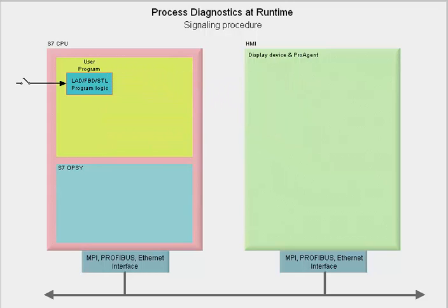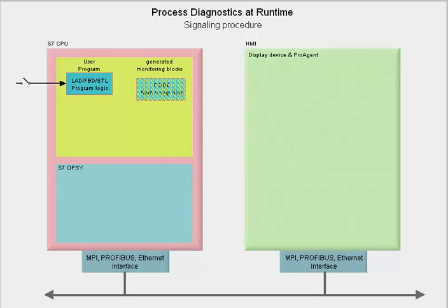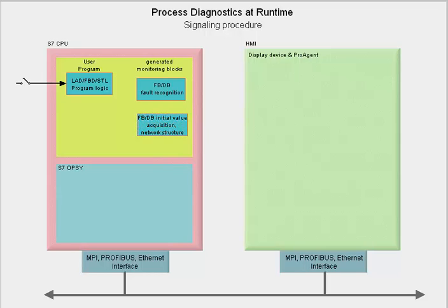As mentioned before, the S7-PDIAG option package generates the functions and instance data blocks for this configured address monitoring. The first function block has the task of monitoring the address in its set point state. The second function block stores at the time of fault the state of all the signals that make up the result of logic operation of the address being monitored.